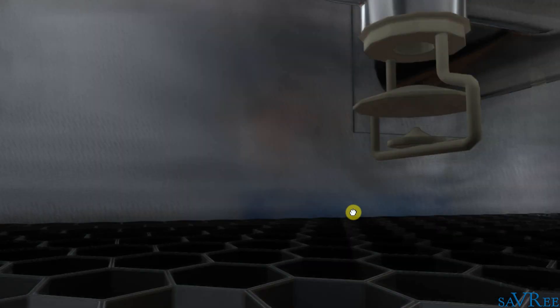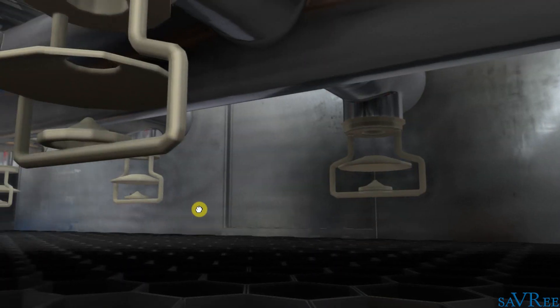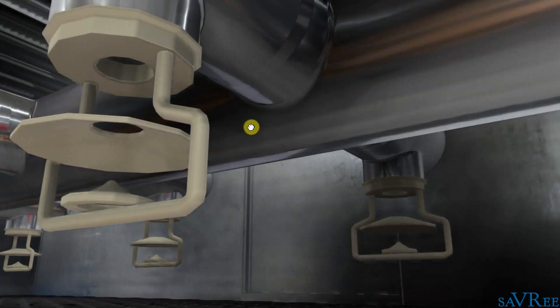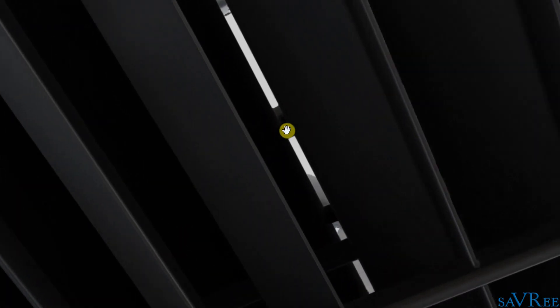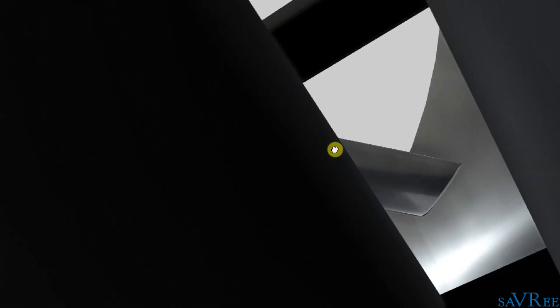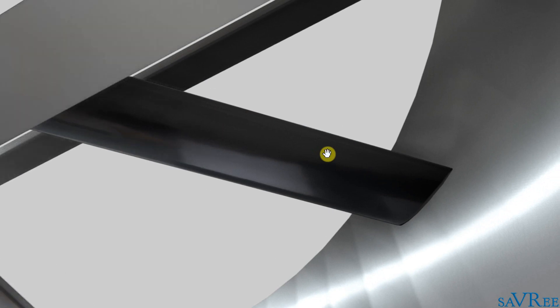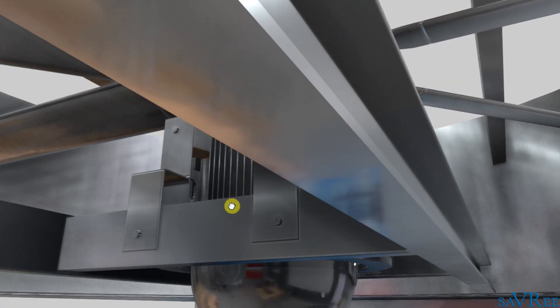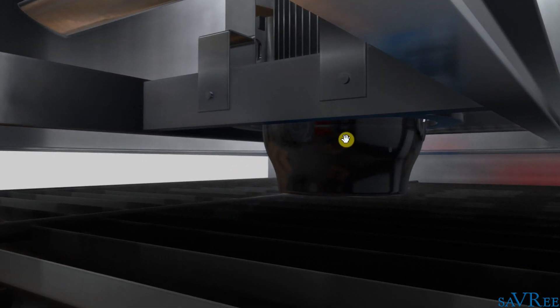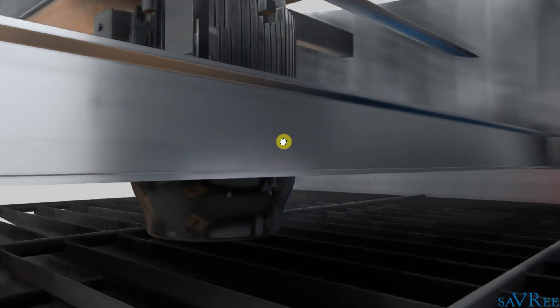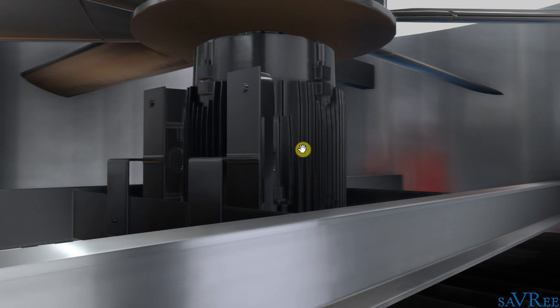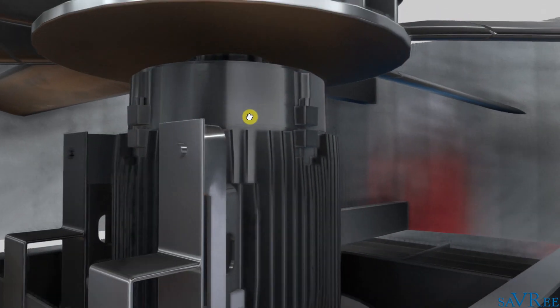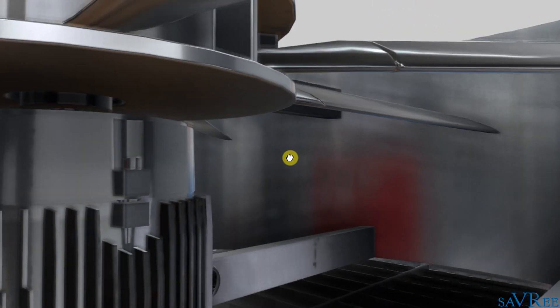There's our spray nozzles again. We'll do a little spin here. And now the air is going to be drawn up even higher through the tower. We're going to pass through this black item here. This black item is known as a drift eliminator. Let's pass through. We have to change direction slightly here, it's not a straight run. And then we're through the drift eliminator. And where are we now? We're actually at the same level as where the fan motor is installed. So we can see we've got an electric motor, this is a three phase AC electric motor, and then we're going to pass through the fan.